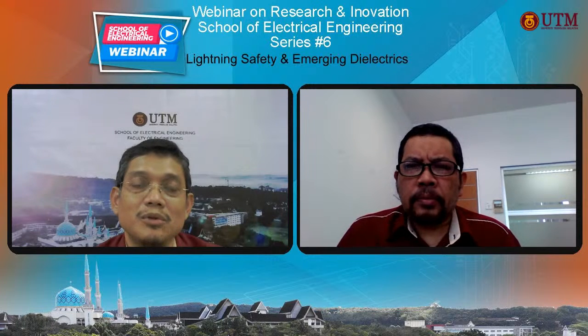As you can see, the air terminal is supposed to intercept lightning and then safely discharge it to ground through the down conductor. There are many claims that you can make the air terminal intercept lightning current but at the same time reduce the current to a very low value. We call it SLE, or semiconductor lightning eliminator. This way you minimize the magnetic field associated with large current flow on the down conductor, and therefore you are safe from this high current flow.